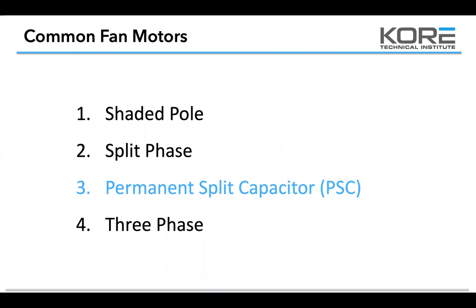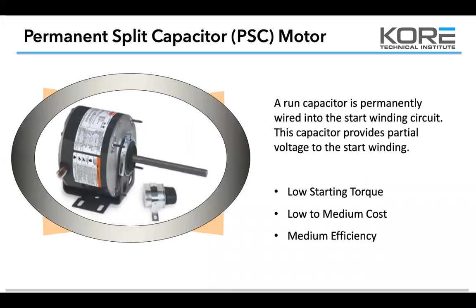So PSC motors, permanent split capacitor motors. Again, we deal with these a lot. Condenser fan motors. A permanent split capacitor is going to have that run cap in play. Where you have motors, you've got your 3 leads or you have multiple leads. You might have directional leads, like where you have the spades on the bottom of the motor where you can switch it clockwise or counterclockwise. So you're usually going to have 4 leads for your rotation. And then you're going to have up to 3 speeds and a common for your motor. And then you're going to have those 2 brown wires coming out for your capacitor. So indoor blower motors and condenser fan motors are where we see most of these.